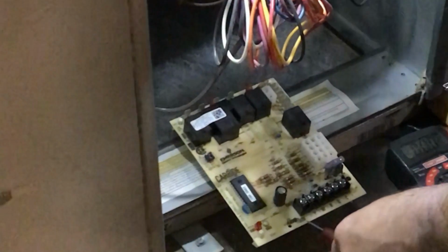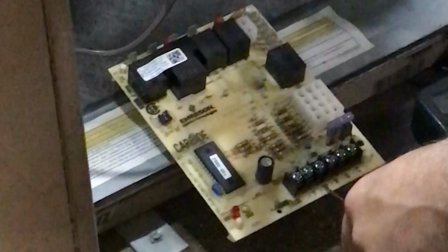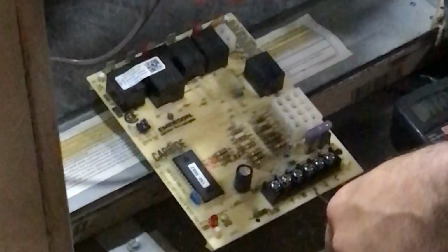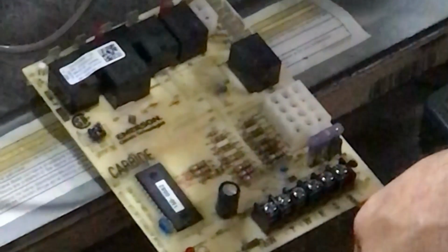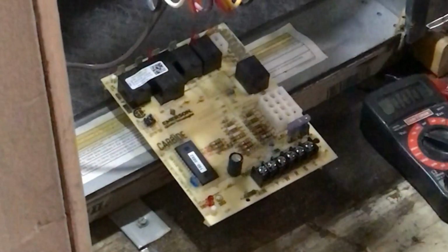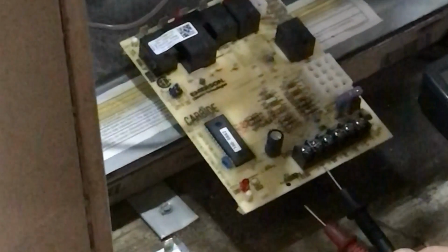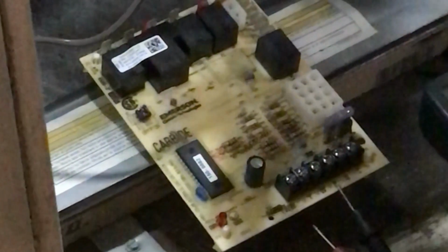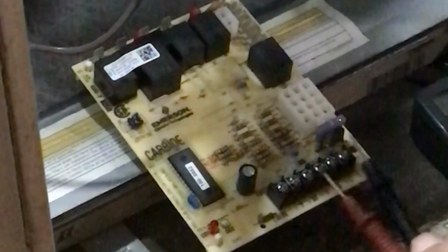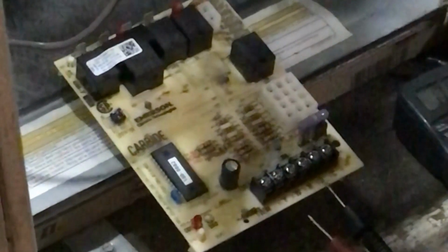Alright, so on your circuit board on the bottom here, you're going to have a Y terminal, yellow, W for white, R for red, G for green, and a C common. Typically it's going to be a blue or a black wire, but depending on what kind of wire they used, it could be any color. Yellow is going to your AC contactor. That's going to energize your AC contactor. White is going to energize your heating system. Red, like we said earlier, is the power wire that the board distributes to the different terminals and the thermostat. Green, your fan. And C is common.